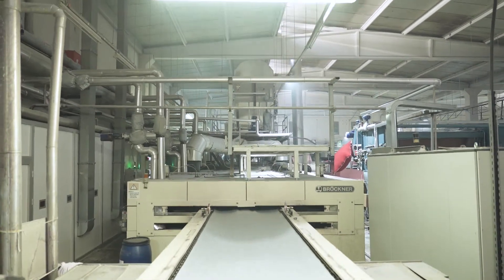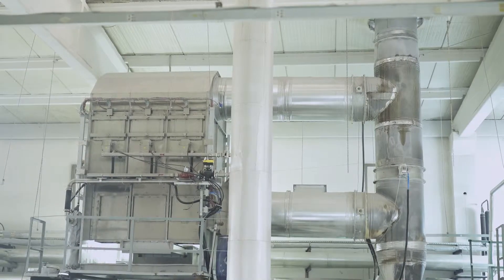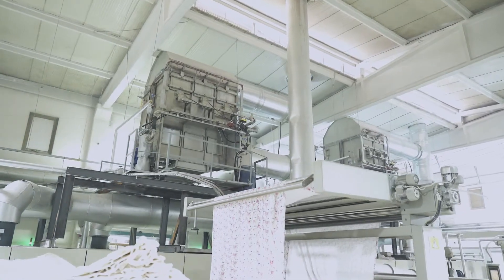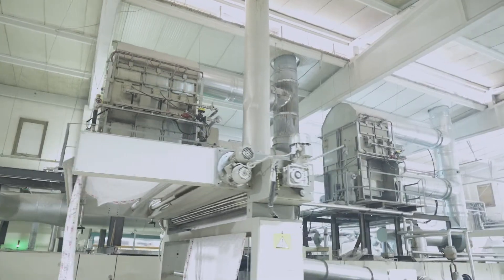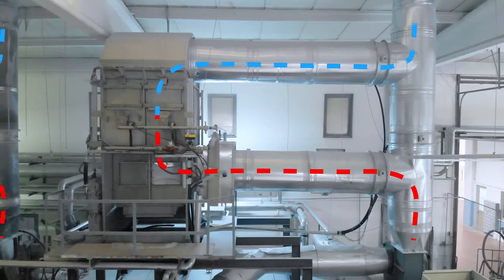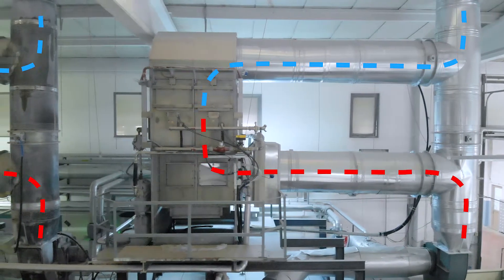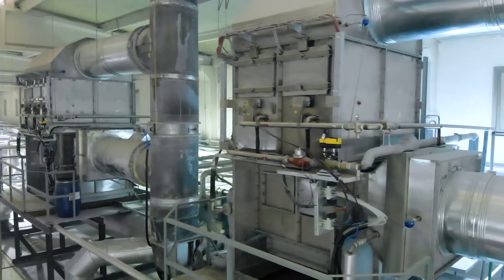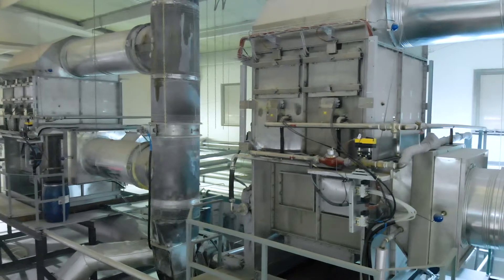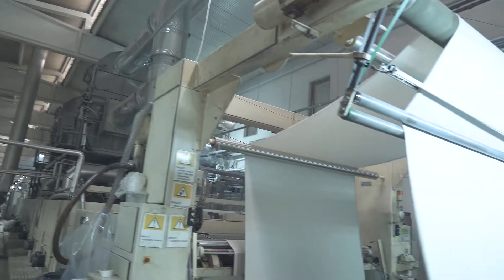The hot gas emissions of stentor machines are filtered and an efficient heat recovery is provided in the ESP 600 filter unit. VanTerm ESP 600 filter units are produced in 304 quality stainless steel. The electrostatic filtration technique is used in ESP 600, therefore the total pressure loss is very low and it is often enough to use existing ventilators on the stentor machine. In most cases there is no need for an additional ventilator.